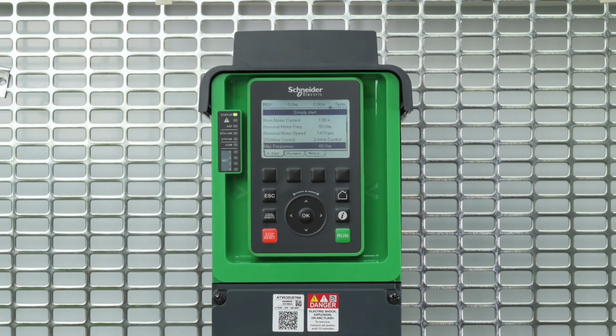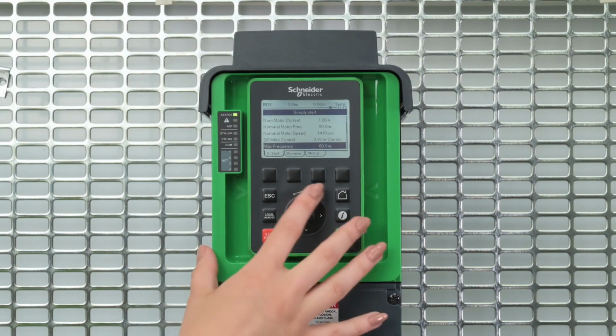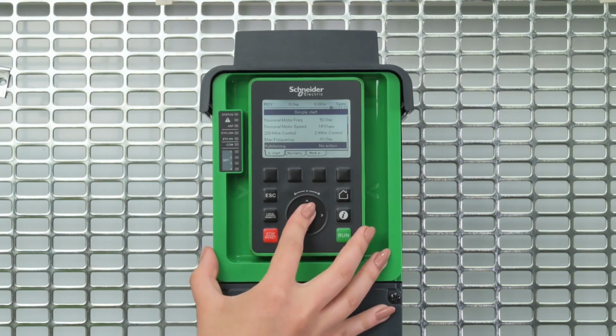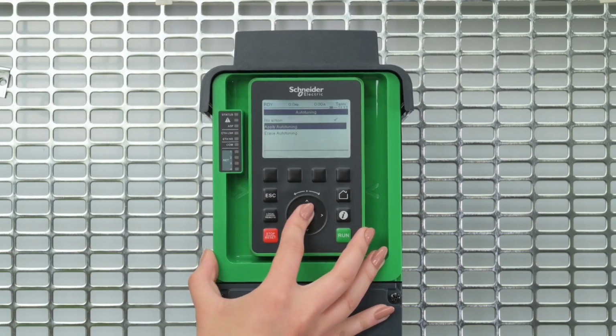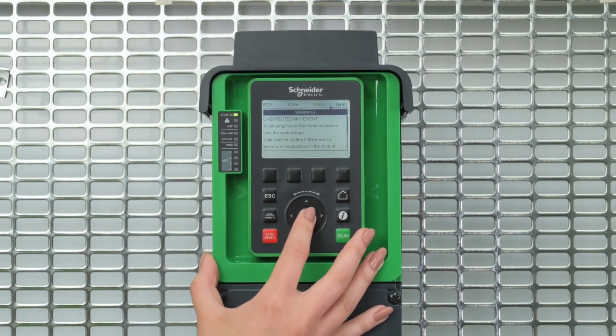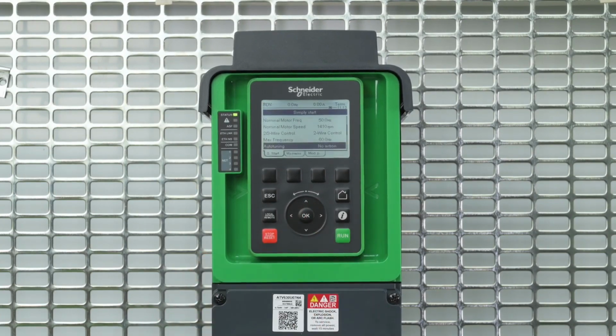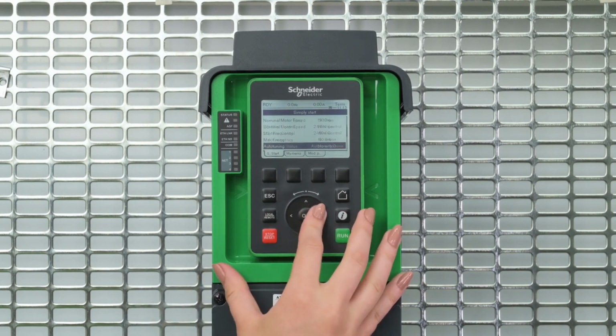Once all these parameters are set, you will have to perform an auto-tuning procedure, allowing the drive to refine the motor characteristics. This will create a small noise in the motor, which is totally normal. If you modify the value of one or more parameters after having performed auto-tuning, the value of auto-tuning status resets to Not Done, and you must re-perform auto-tuning.